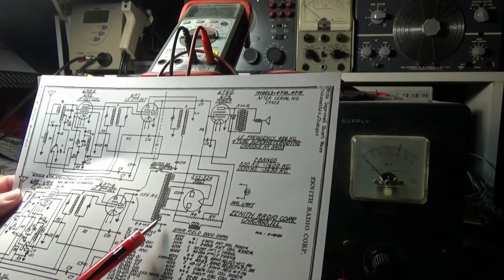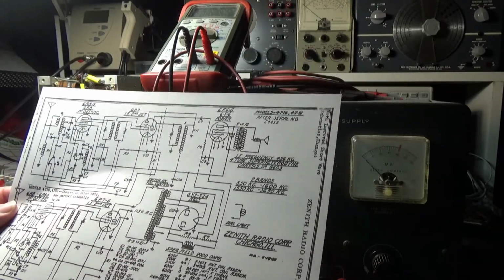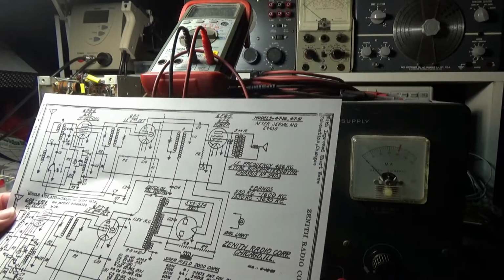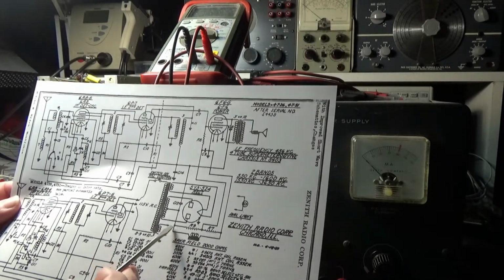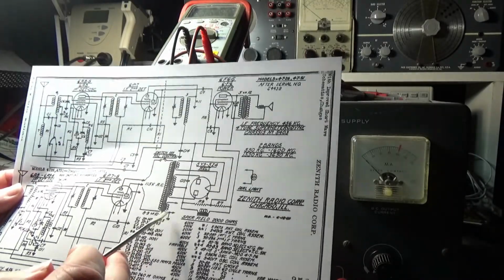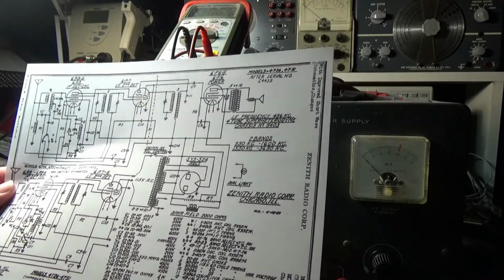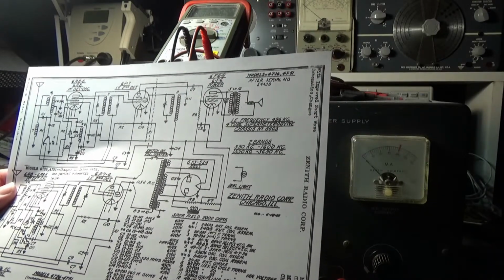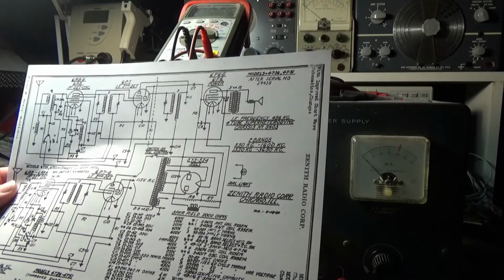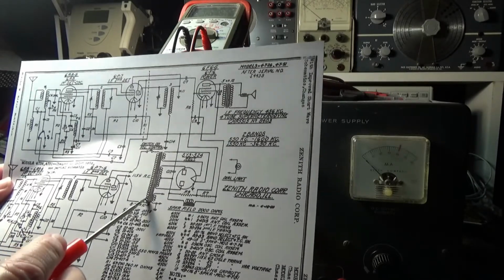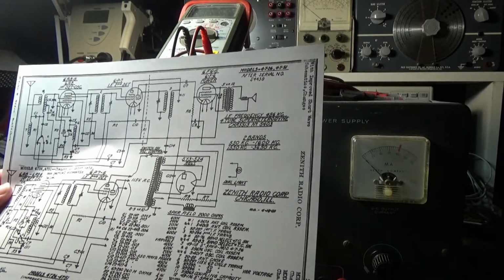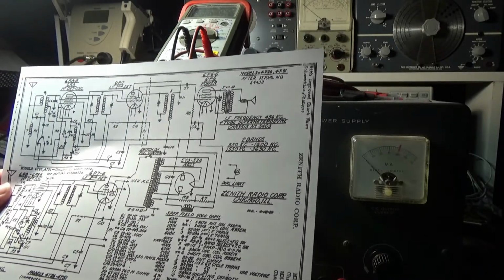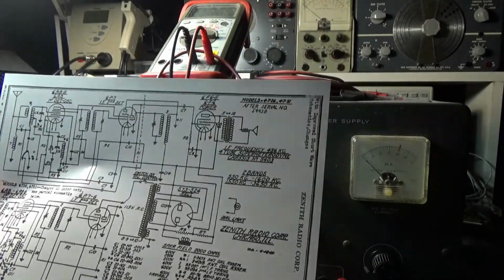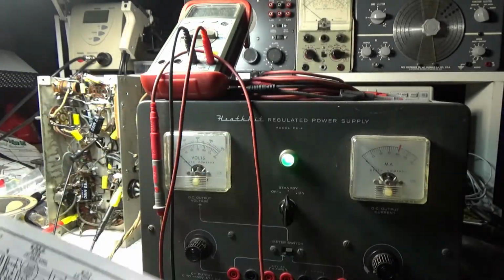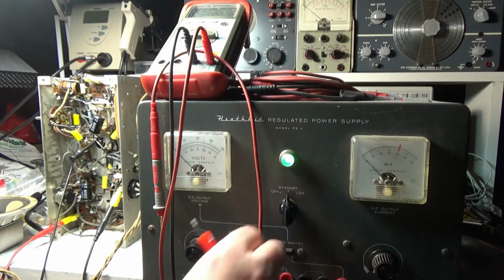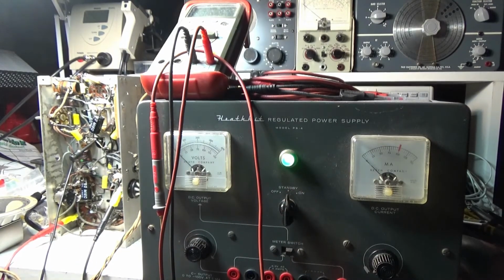So my next step is to disconnect this, then plug the transformer back in and monitor the amperage. If the amperage goes down, we know there's a problem either with the wiring or with this part of the transformer. I'm suspecting the problem is here on the primary side for some reason - I don't know why, but I do. I'll come back once I get those wires disconnected, monitor the amperage, and get this power supply out of here. We'll show you when I get to that point.